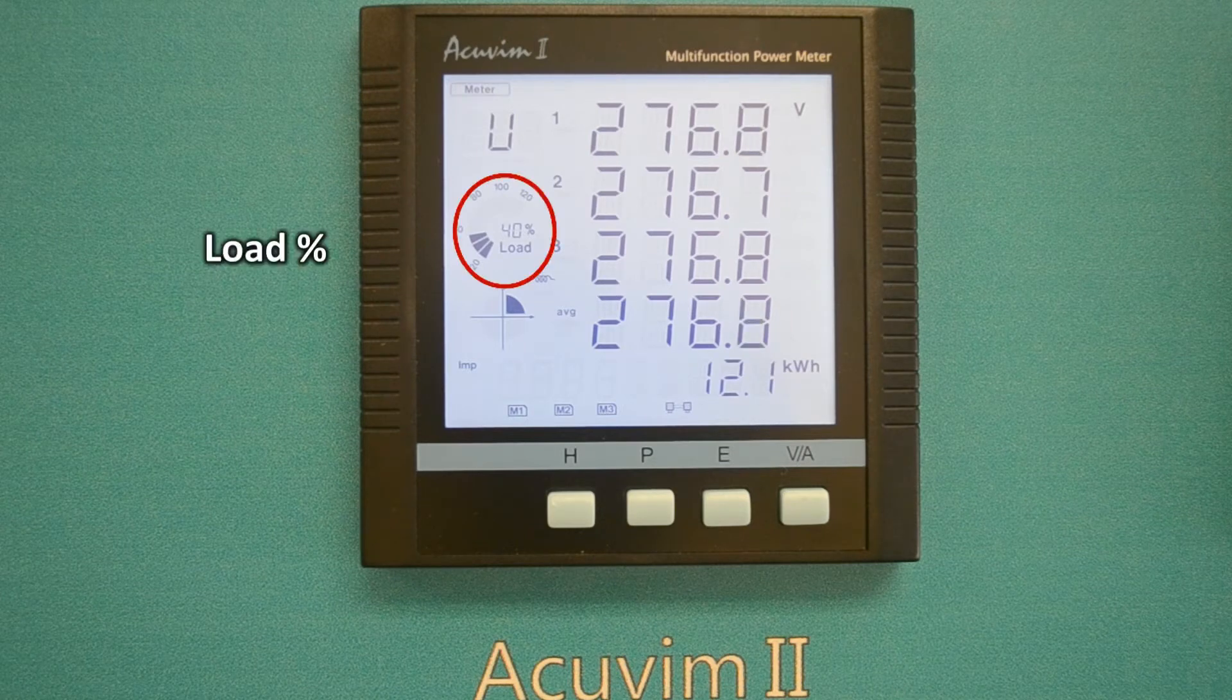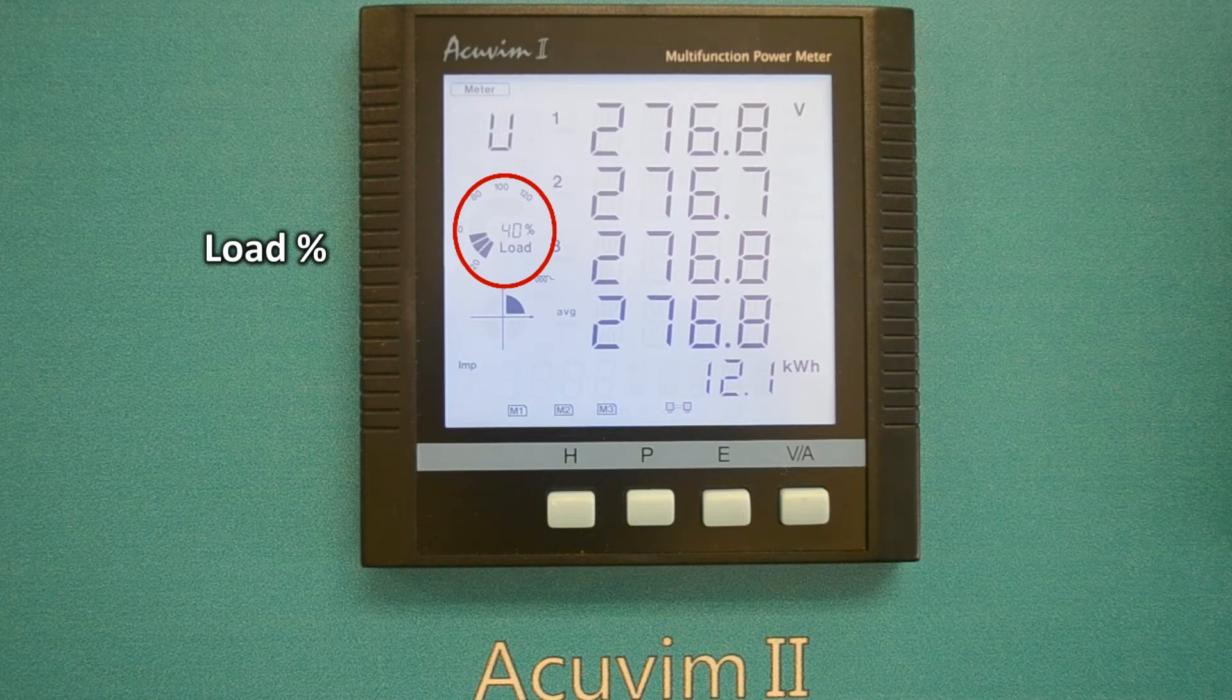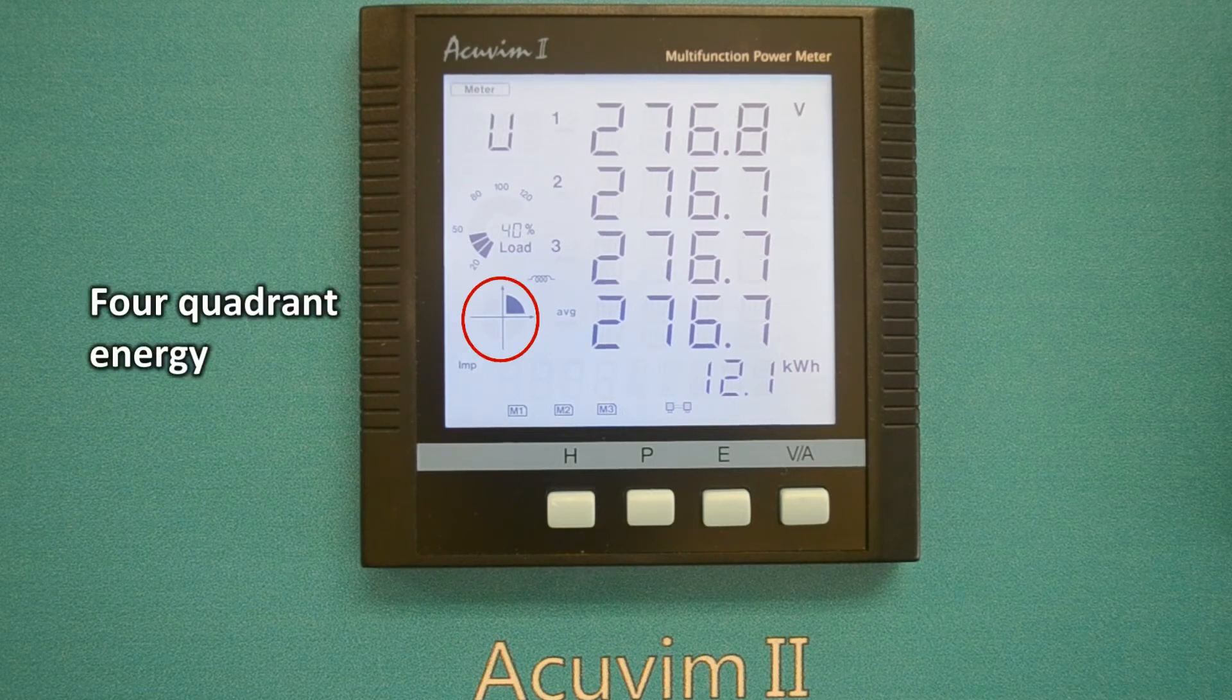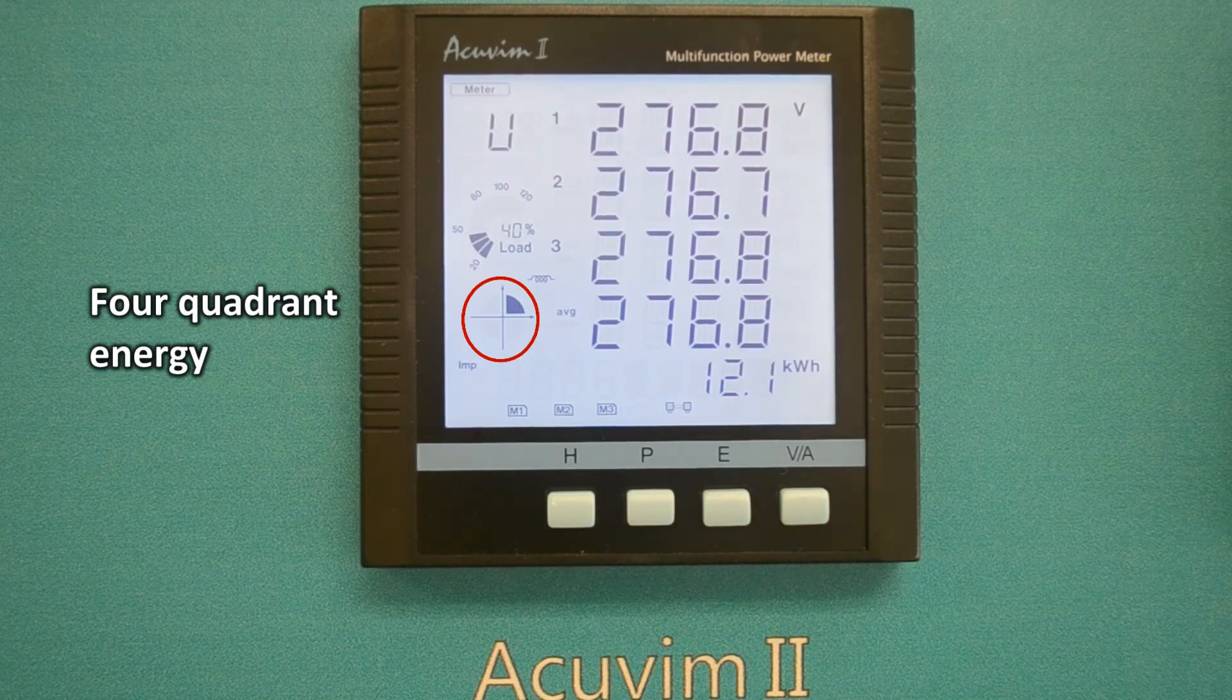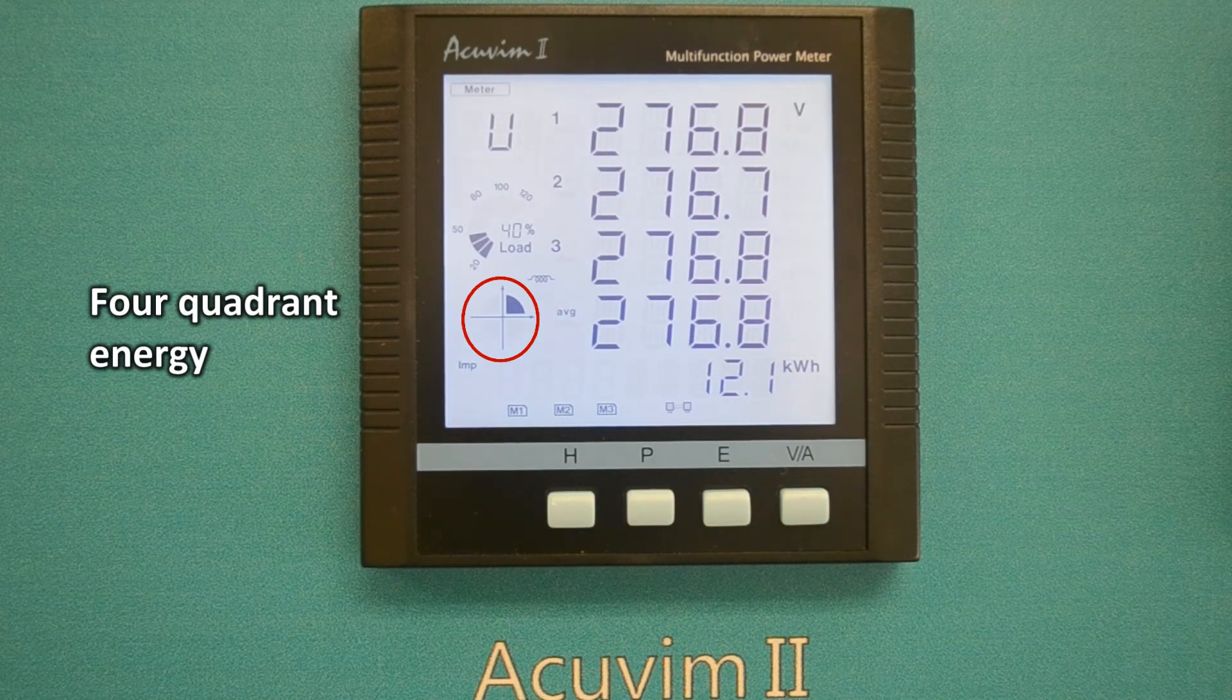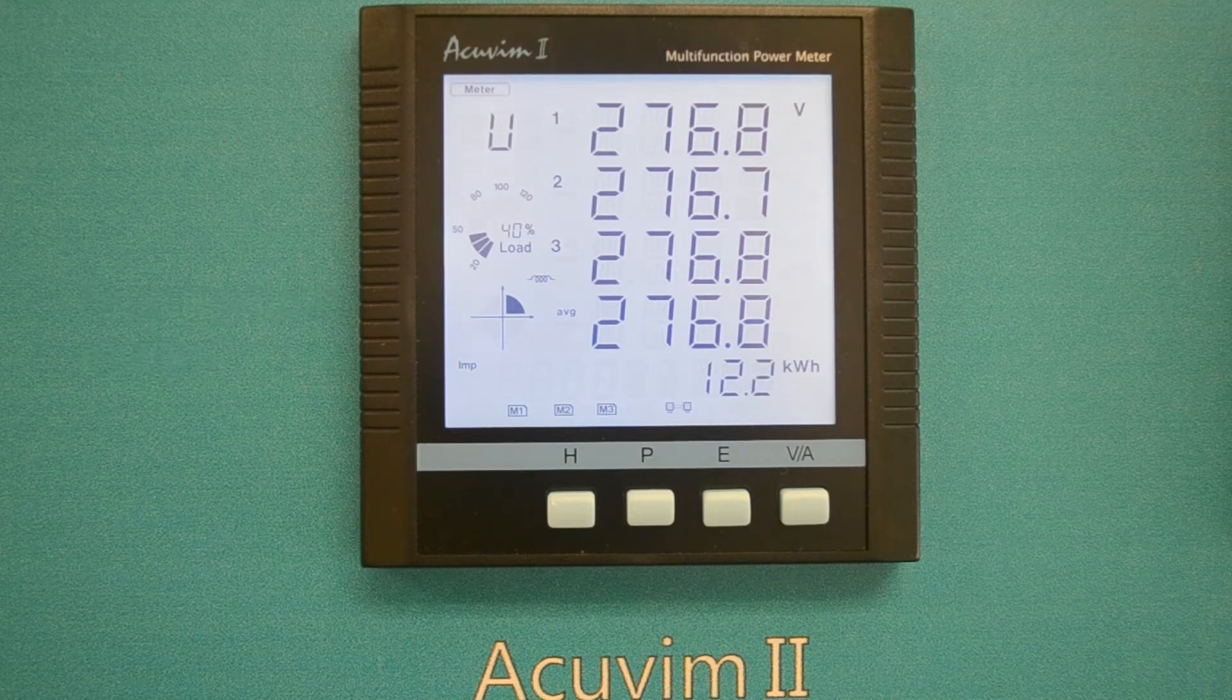The load percentage indicates the percentage of load current to nominal current. The four quadrant graphic displays four quadrant energy conditions. At the moment, the meter has lit the first quadrant, meaning the power factor is lagging.